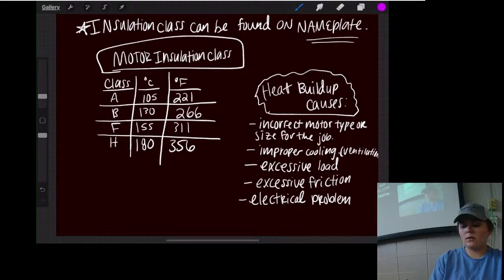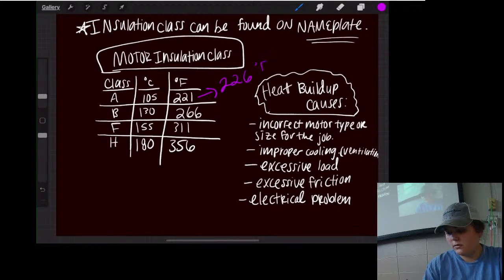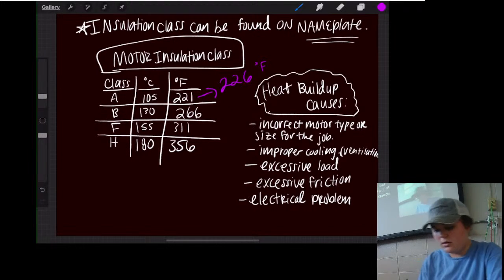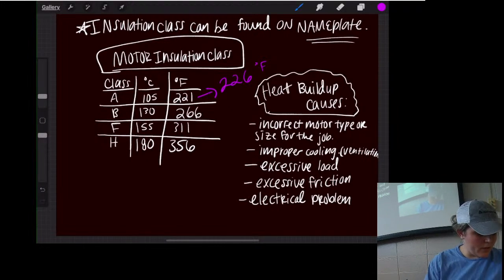So these are the different types of classes. If you're running this motor and it's a Class A, running at 226 Fahrenheit, that insulation is going to start melting away, right? It's not rated for anything higher than 221. Let me just look it up — well, you can see it right here.